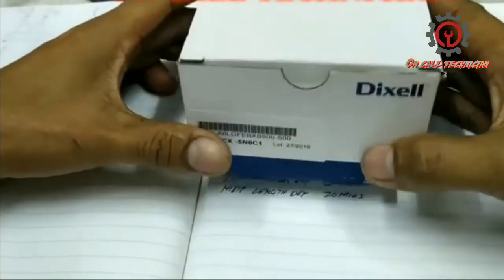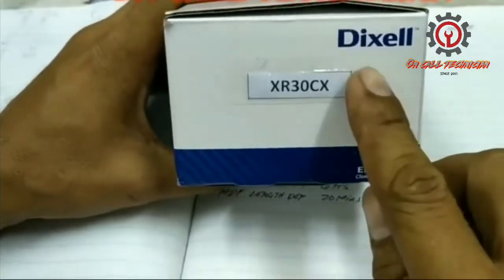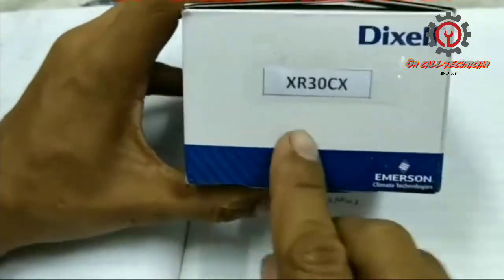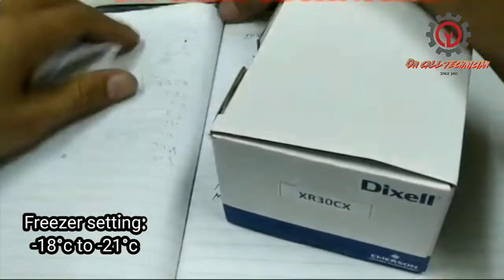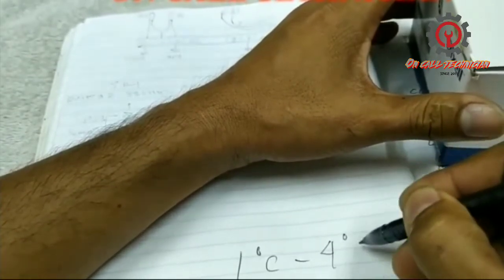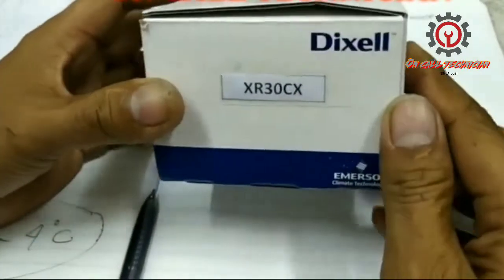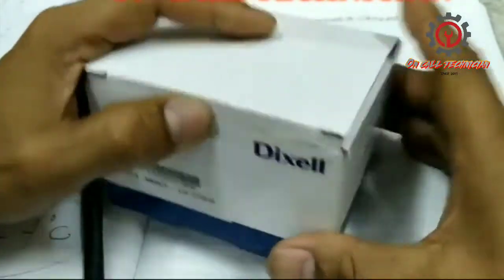Welcome to my YouTube channel. Today we're going to unbox and program this Dixell XR30CX. This model is intended only for chiller setting and it's not applicable for freezer setting because it has only one sensor, which is the room sensor. For a freezer, it must have both a room and evaporator sensor. Our chiller setting is between one degree Celsius to four degrees Celsius, and this is under HACCP standard.